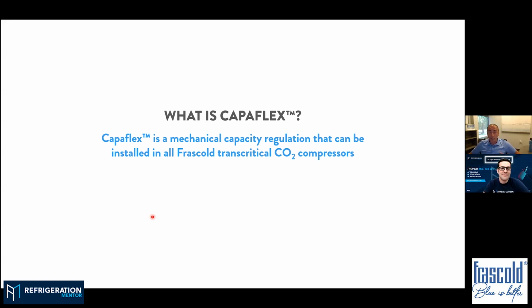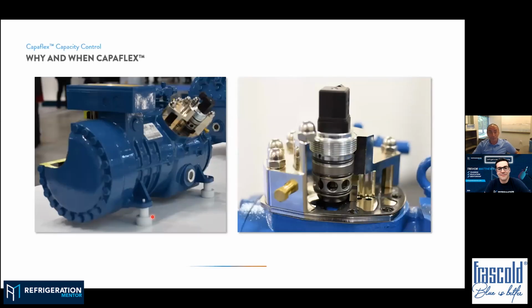In CO2 systems we hear a lot about VFD, but not much about mechanical capacity control. I think the main reason is that it's very difficult to design something that really works properly. But anyway, this is how our capacity control looks for this compressor. This is a cutaway of a real compressor - a 2-cylinder on the left and only one cylinder on the right.